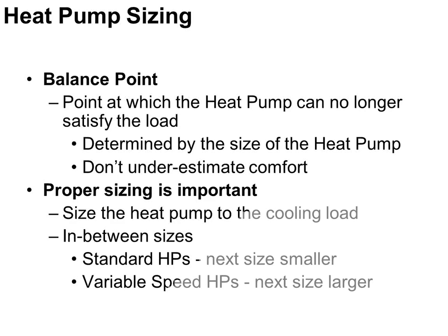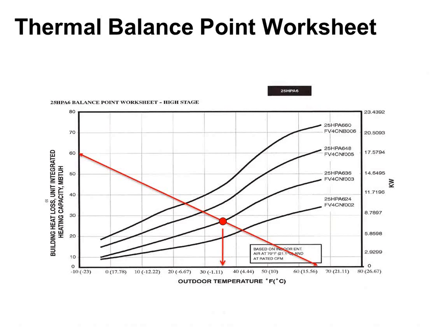So the one thing that we change on variable speed heat pumps in terms of sizing compared to traditional heat pumps is I round up to the next whole size typically, assuming that my ductwork system can handle the airflow required. If it's a new system, no problem. If it's existing, you got to look at it. There's a couple different ways you figure out the balance point. I usually use a software tool to do it, but that doesn't work quite as well on the webinar. So I'm showing you the old school graphical method here.